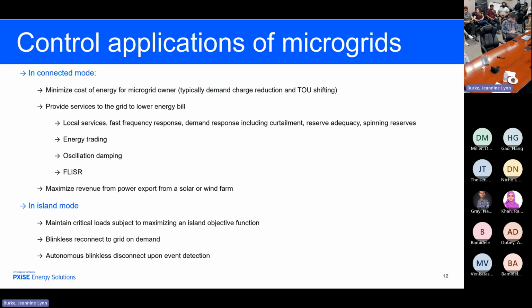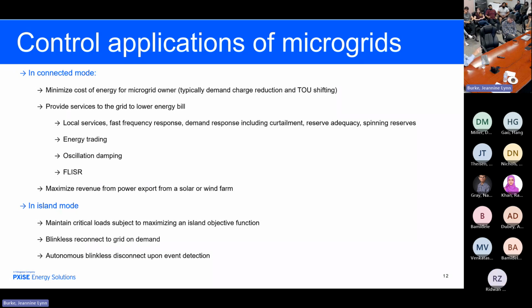So this summarizes it. If I'm in connected mode, I want to be able to minimize my cost of energy. And that's typically done by calculating the optimal POI real power flow at the point of interconnection to minimize my demand charge. And in California, we have very high demand charges, $45 per kilowatt. That's a lot to pay per month if you exceed a limit. So you need to control demand. And we also have high time of use charges. So you want to shift the load consumption, shift your import as far as possible to the minimum time of use zone. And of course, you also have to figure out how big your battery should be to do that. So that's the main objective.